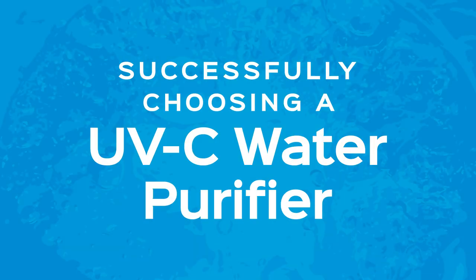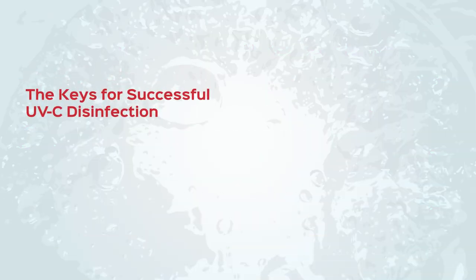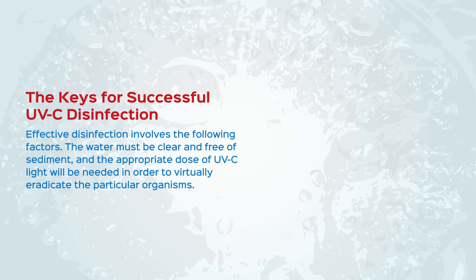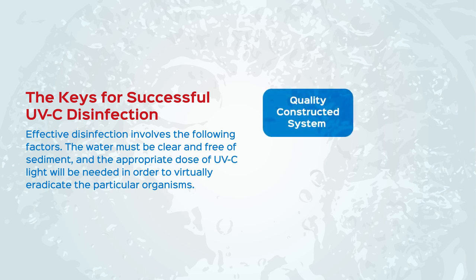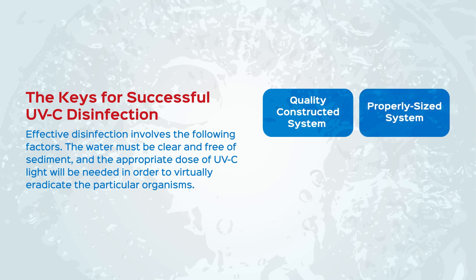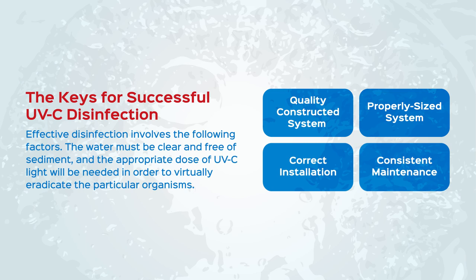Successfully choosing a UVC water purifier. Effective disinfection involves the following factors: the water must be clear and free of sediment, and the appropriate dose of UVC light will be needed to virtually eradicate the particular organisms. You'll need a quality constructed system, the properly sized system, correct installation, and consistent maintenance.